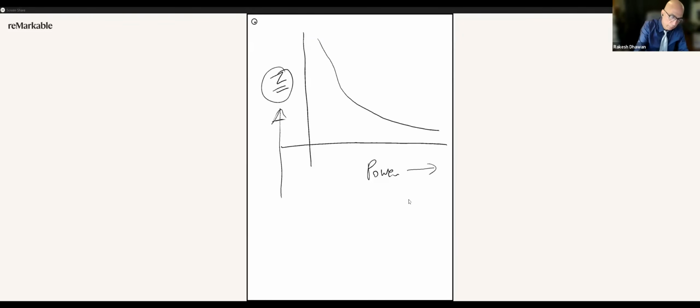And your switching frequency similarly comes down, following essentially the same curve, because at least today, you still have efficiency issues if you're trying to switch at higher frequency, right? So the switching frequency goes down. You're down to 2 kilohertz here, and you may be up to 20 kilohertz here.